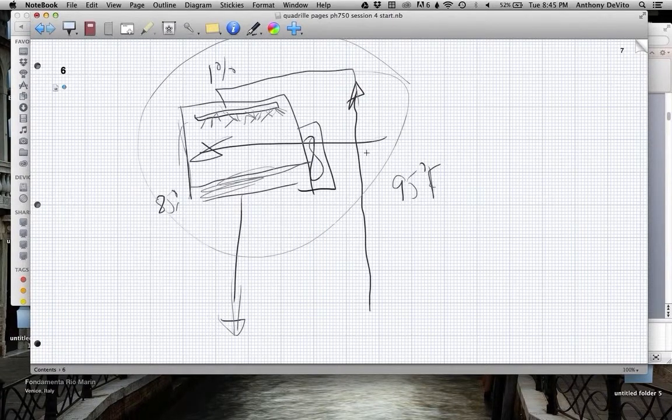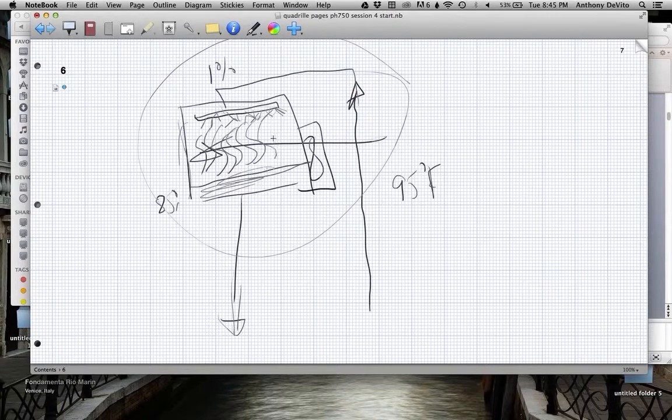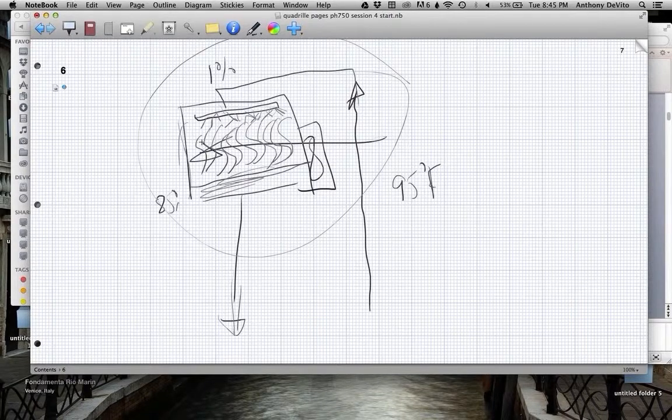That's what those cooling towers are. Inside the cooling tower, they also have a corrugated material, sometimes PVC, used to be wood, and so on and so forth. It's in there because when you spray the water on, it forms kind of sheets. So when you blow the air through, you get more surface area between the air and the water rather than big droplets. So that gives you a mechanism for cooling the water.